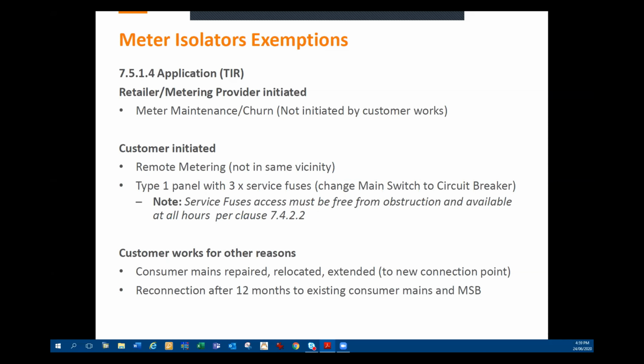For a type 1 panel as well with 3 service fuses, we've put an exemption there to change that main switch for a circuit breaker. So that saves having to replace the whole panel or do a major alteration just to get a meter isolator on in that case. But the service fuses as well must be free from obstruction and available at all hours per clause 7422. And if it happens to be customer works for other reasons, consumer mains repaired, relocated or extended to a new connection point, they don't necessarily need a meter isolator.